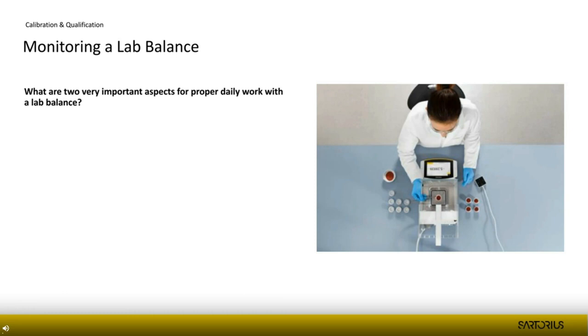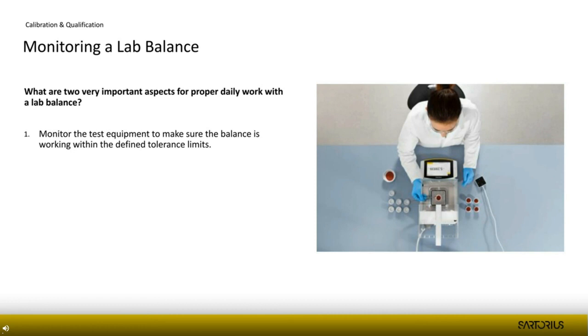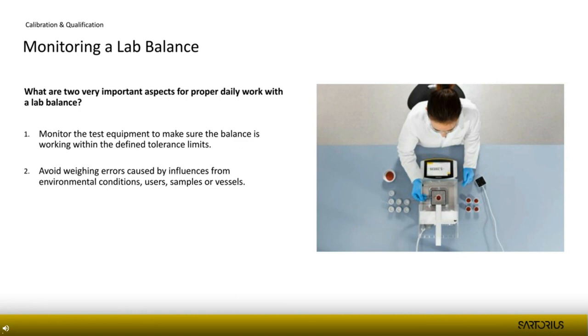Let's look first at the two main reasons to monitor a lab balance. The first is working with defined tolerance limits — when we exceed certain limits according to regulations or internal operating procedures, the equipment should remain inside those tolerances. The second is to avoid weighing errors caused by influences from environmental conditions such as airflow, vibrations, and also from users, the sample itself, or the vessels containing the sample.